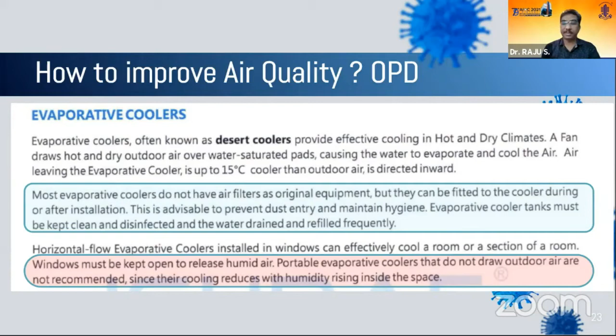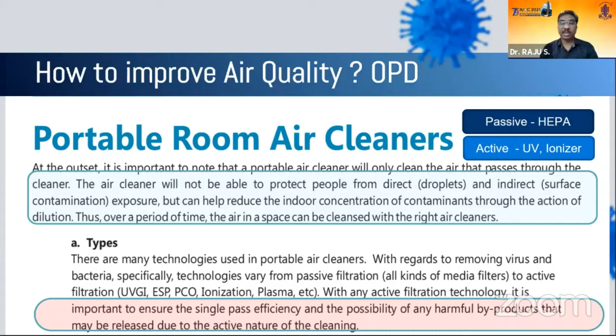Coming to the portable room air cleaners, again there are two types. You have the passive type, that is the HEPA filter types, and the active type, the UV and the anionizer types. It's important to understand they will not protect people from direct droplets or surface contamination exposure, but will reduce the indoor concentration of the contaminants through the action of dilution. So they'll remove these contaminants, hence make the air less contaminated. When you are using active systems, we have to make sure that we understand the single pass efficiency of that system and also the possibility of harmful byproducts.